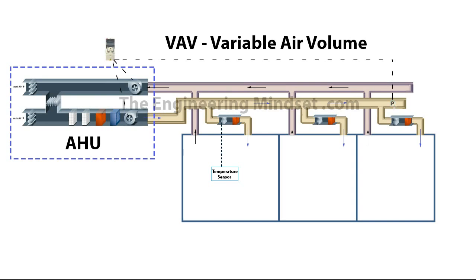So what we want to do is fit a pressure sensor here towards the furthest point in the duct to get the most energy efficient operation. And these are connected over to the VSD, the variable speed drive or the variable frequency drive. The VFD is connected directly to the fans, the fan motors. And the VFD will then slow the fans down, slow the induction motors down.